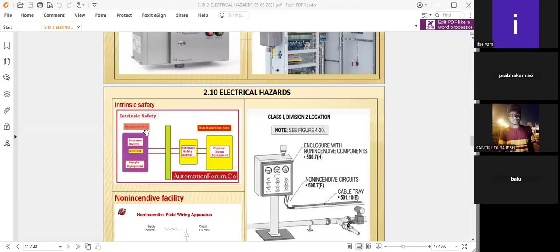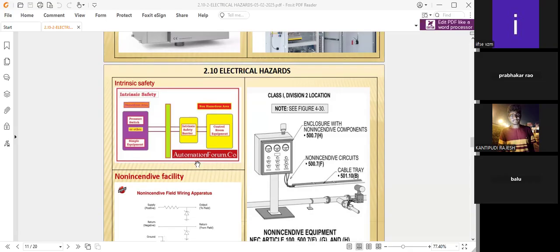See, for example, in hazardous areas there is a pressure switch or other simple equipment like this, some auto-proof, auto-function arrangement, like intrinsic safety. Like this, some area is non-hazardous and this area is hazardous. Some barrier has to be taken care of. In this area also electrical panels are there, and in this area also electrical panels are there. But if you are not providing the barrier to both sections, definitely it will not be covered by intrinsic safety. It means intrinsic safety is not much influenced in that organization.